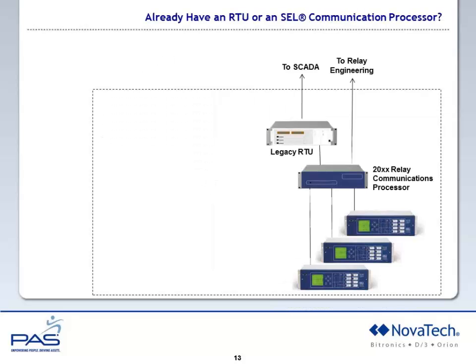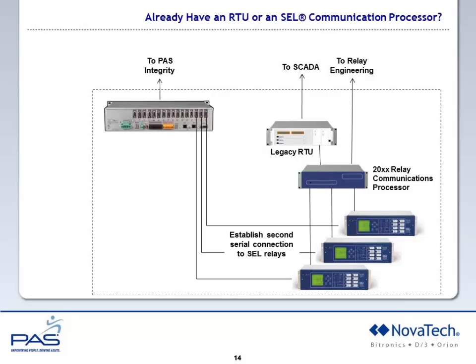Now, some of our customers have asked, what if I already have an RTU or an SEL communication processor in the substation? What if I have something that looks like what's in the diagram there, a legacy RTU talking to SCADA, maybe a 2030 or 2020 communications processor connecting through to relay engineering? In that case, it is possible for many, if not most, of the Schweitzer relays to establish a second connection. We do need to use the SEL protocol in order to access the settings files.